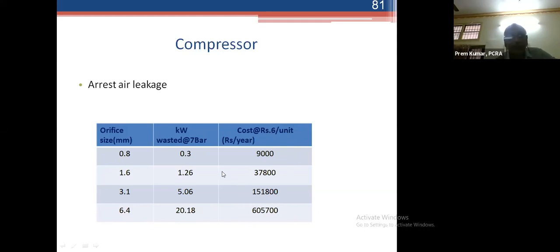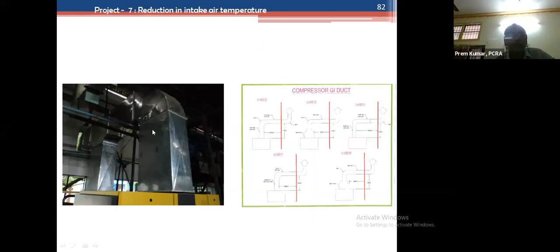So ensure that you attend to leaks at the earliest opportunity and create awareness among the machine users and operators. So this is one area where the hot compressed air is being exhausted out. This resulted in a good saving for the compressor. The company was planning to expand by buying a new compressor, but this was stopped by this measure. One more measure they could have done is to insulate this, which could have resulted in further savings.